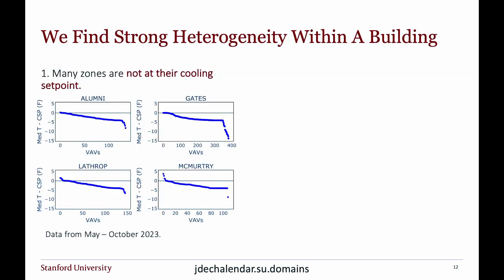Okay, so next I want to zoom back down a bit. This is tugging a bit on what I was saying about the temperatures not going up by 2 degrees or 4 degrees, not even close to 4 degrees, when I increase the temperature set point. One of the things we also found when we look at this zone level data, and this is why I think it's so rich to have zone level data, is that a lot of the zones are not at their cooling set point.